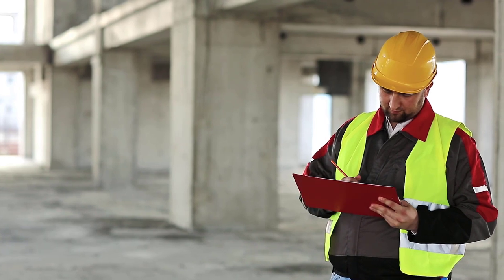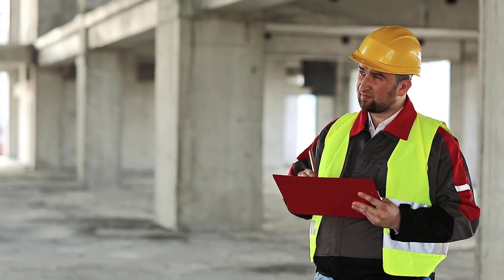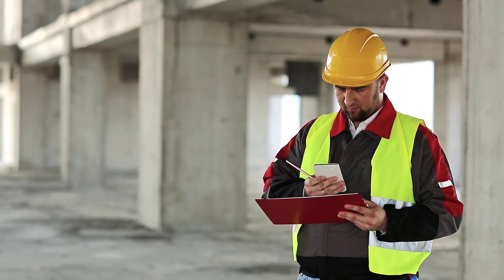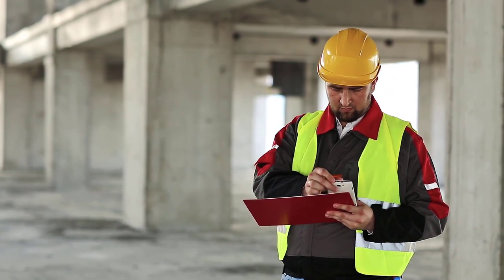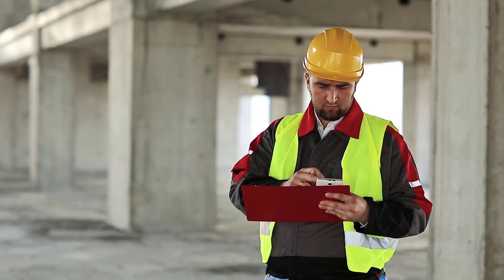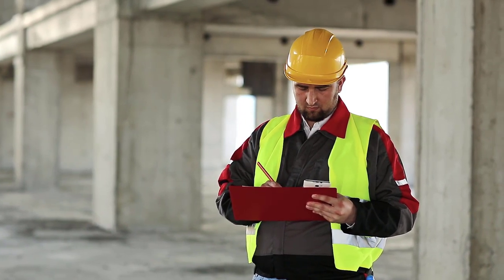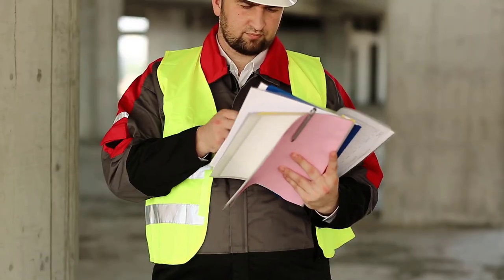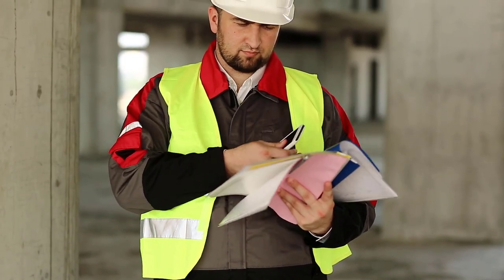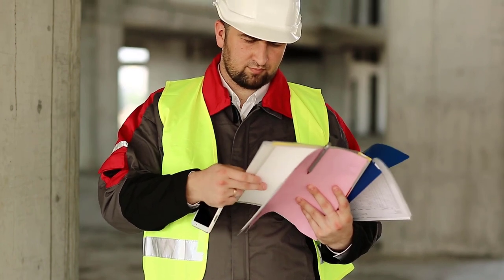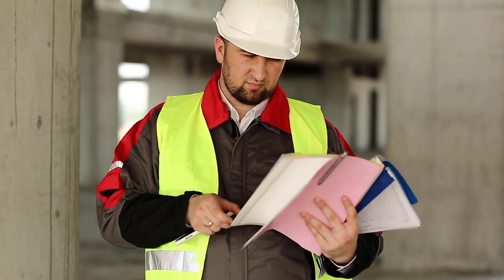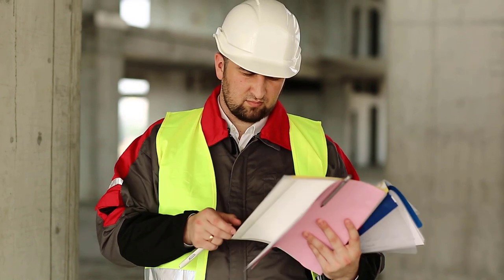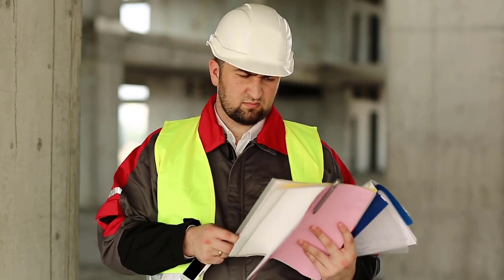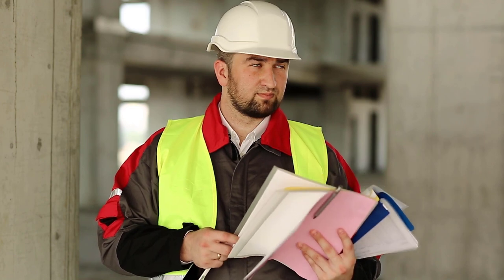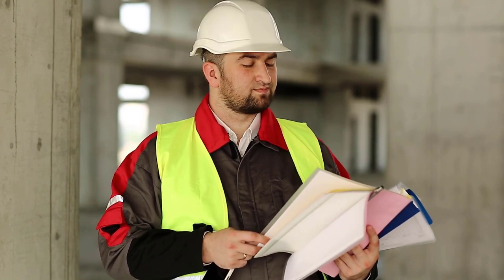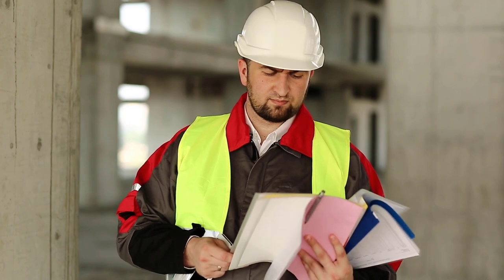Where a site safety manager or site safety coordinator is required by the building code, the owner shall designate a person to be the fire safety manager for the construction site. The fire safety manager may be the site safety manager or the site safety coordinator required by the building code. The fire safety manager shall be responsible for ensuring compliance with the requirements of this code, including this chapter and the rules of the fire department. The fire safety manager shall conduct an inspection of the construction site on a daily basis and maintain record in a bound logbook.